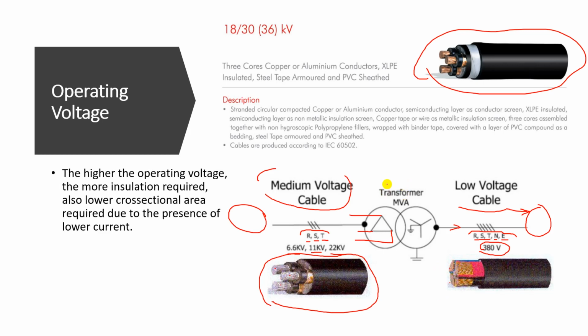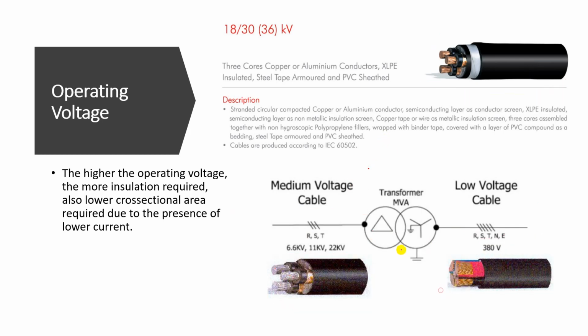Now, you will notice two important notes here. If you compare the cross-sectional area of the core, or the conductor itself, you will find that the cross-sectional area of the medium voltage cable is smaller than that of the low voltage cable. We also find that the insulation size here is larger than the small insulation here.